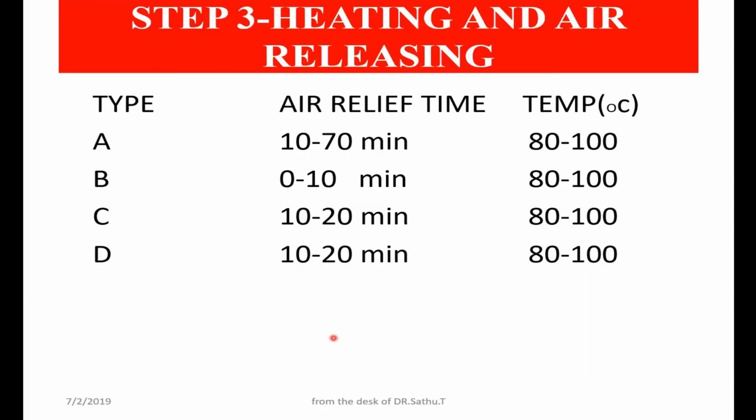After charging, we go for heating and air releasing. The steam will be injected into the double space, so slowly the heating will take place, and the non-condensable gases inside the cooker should be removed. I just want to compare this with the ordinary cooker that we use at home. Here we use what you call a blow-off valve, similar to the weight that we put on the home cooker.